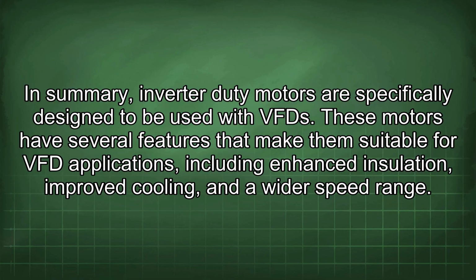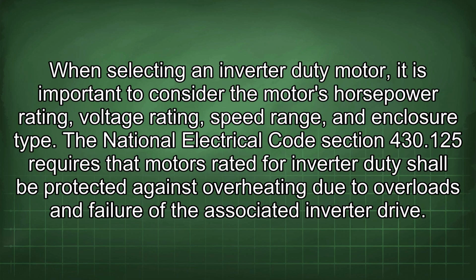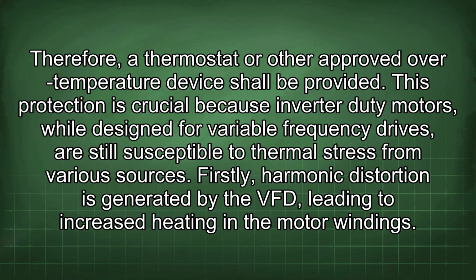These motors have several features that make them suitable for VFD applications, including enhanced insulation, improved cooling, and a wider speed range. When selecting an inverter duty motor, it is important to consider the motor's horsepower rating, voltage rating, speed range, and enclosure type. The National Electrical Code Section 430.125 requires that motors rated for inverter duty shall be protected against overheating due to overloads and failure of the associated inverter drive. Therefore, a thermostat or other approved over-temperature device shall be provided.